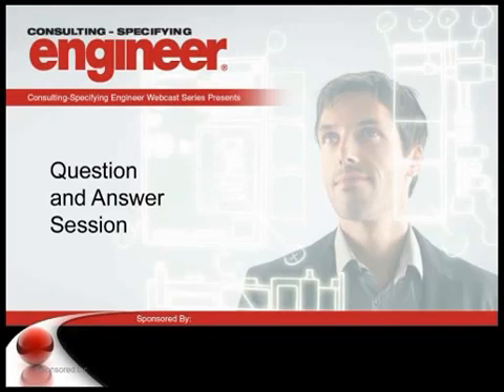Okay. I would also say, in the state of Florida, 0.1 is the threshold for coordination for the Agency for Health Care Administration in Florida. And also there is a proposal in front of the Committee for NFPA 99, which has been approved, to adopt 0.1 in NFPA 99. I don't think it's part of the official code yet, but it's in the process to get there. Okay. Thank you very much.